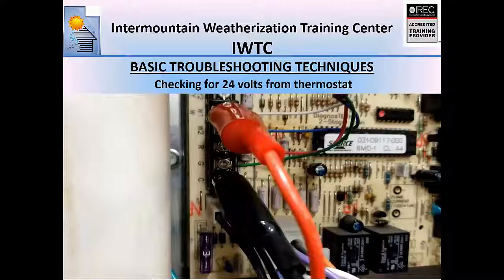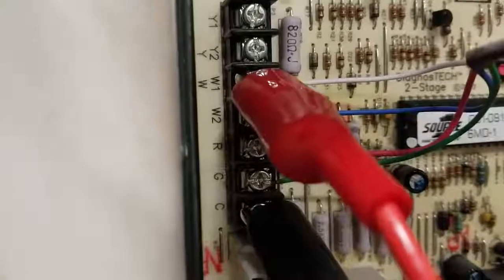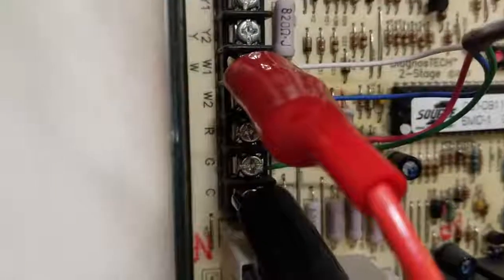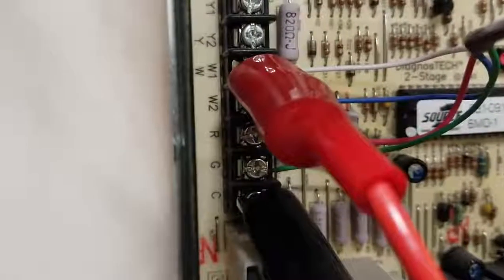Okay, next thing we're going to do is we've determined we have correct line voltage to the furnace. We've determined we have 24 volts. I'm going to show you a quick way to tell if you've got a bad thermostat or bad wiring between the thermostat and the furnace. Real simple measurement, takes just a second to do. Okay, the next thing I'm going to show you is a quick and easy way to tell whether you've got a bad thermostat or bad wiring between the thermostat and the furnace.